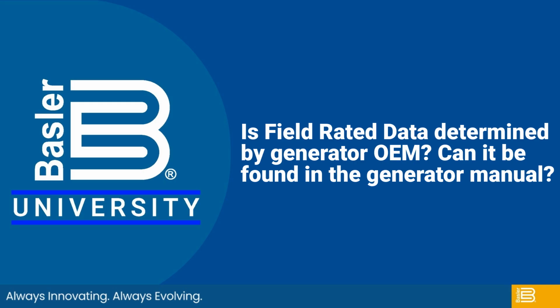The no load values might be available if you have a manual that shows, or some testing results of the machine. You might have those no load values, but it's not typically put on the nameplate. And again, the no load values are typically somewhere close to either a third or a fourth of the full load values for voltage, for field voltage and field current.